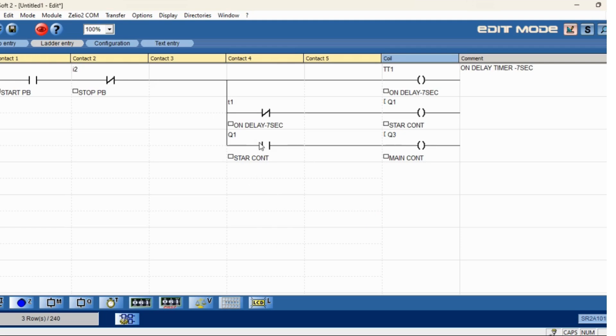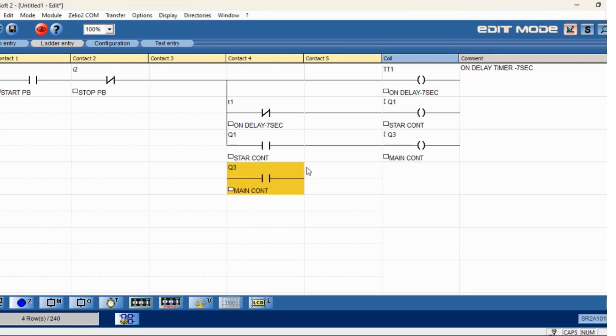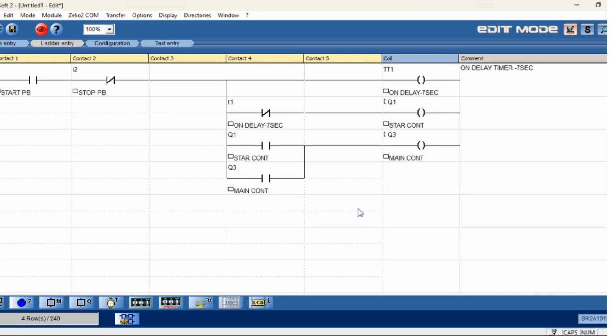Star conductor is enabled and main contactor will be activated. After that we need to latch — once the star contactor is activated, the main contactor will be enabled. After interchanging the star contactor to delta, the main contactor will keep on activated through this latching circuit.